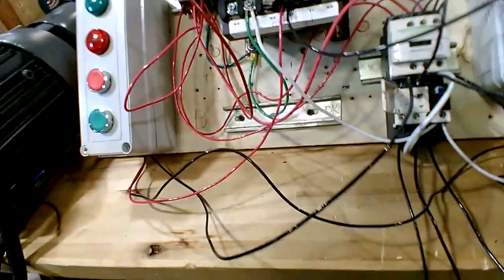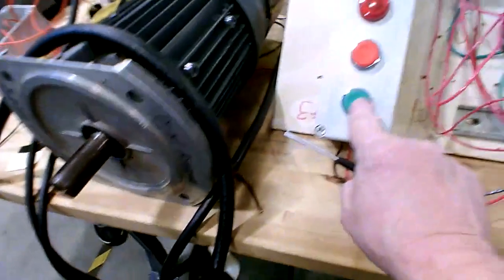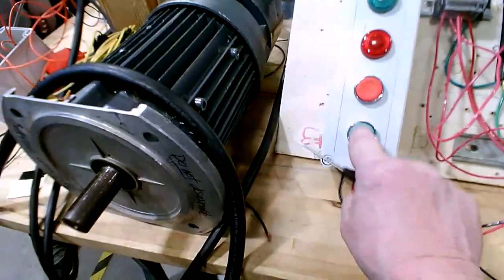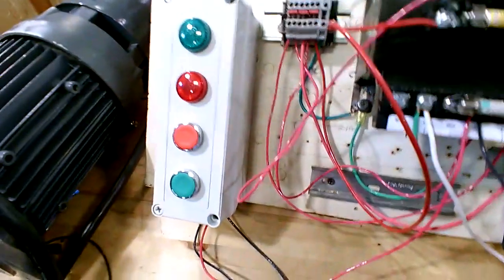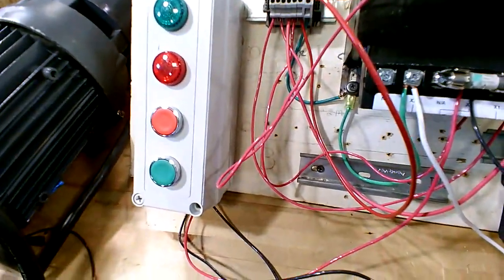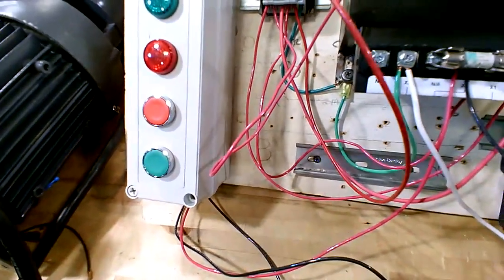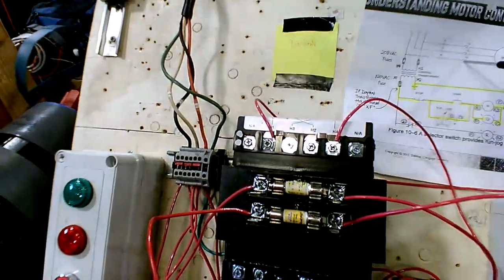Like that, and it says T in there, and it's trip. Now it won't start now. Go right here. It won't start because you have interrupted that neutral right there. You got a hot wire there, but you don't have a neutral here. You got it here, but you've lost it here. That'll pop open right there when your overloads get hot.